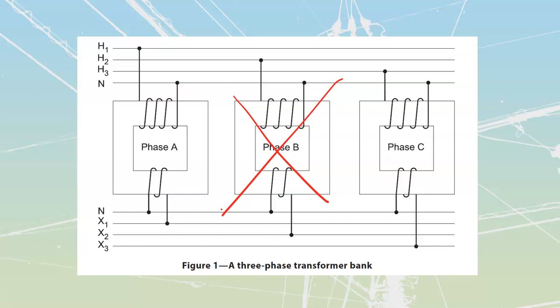We have the ability to continue operating if one unit is broken. Not only do we operate at a lighter capacity, but we also continue operating while waiting for a fix or replacement on that transformer core, so we maintain operation. Also, spares for this are cheaper: keeping a spare single-phase unit around is cheaper than a spare complete three-phase unit. In a lot of industrial locations they maintain a parts storage just in case of a shutdown, because they cannot afford shutdowns - it can cost tens or hundreds of thousands of dollars a day.